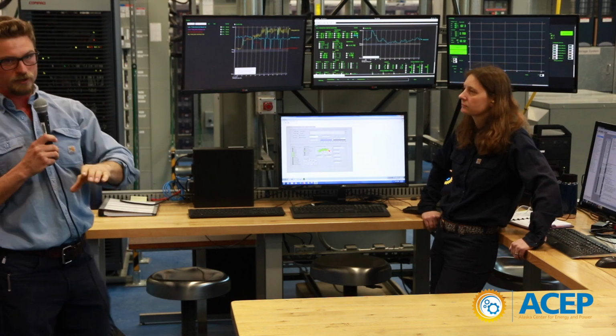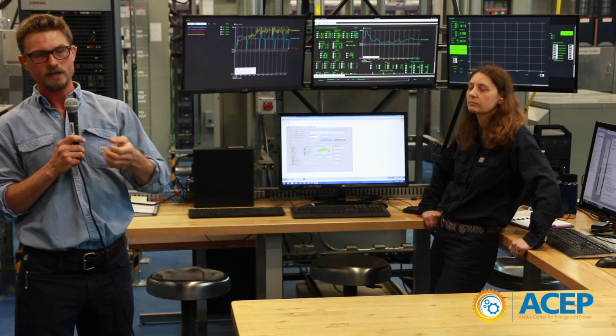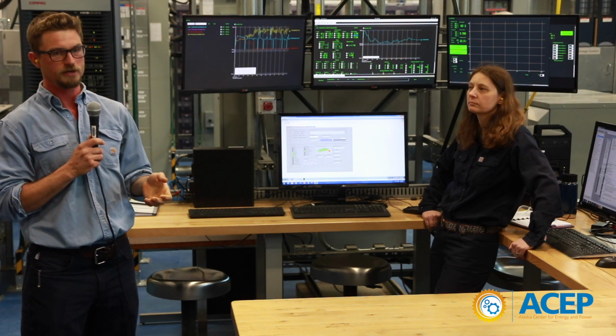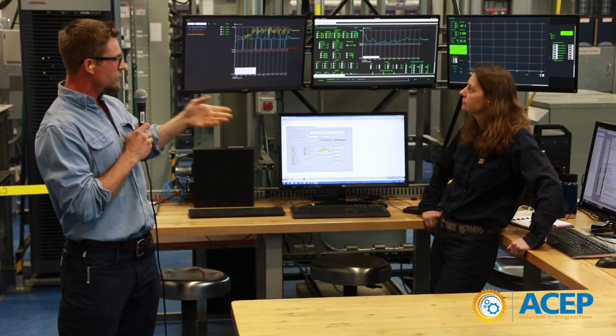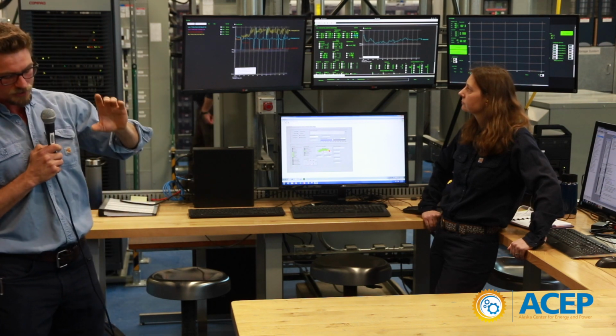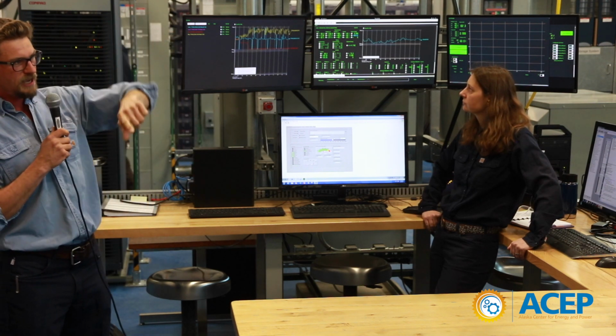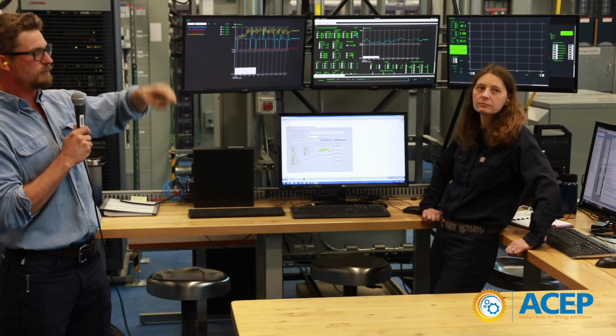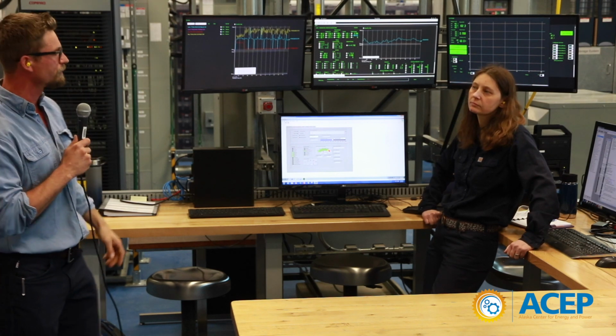What that means is we're low loading our generator. When you low load your generator, the efficiency is lower. You don't get as good of fuel efficiency from your generator. The generator also has a harder time maintaining your system frequency. So your power quality isn't as good anymore.